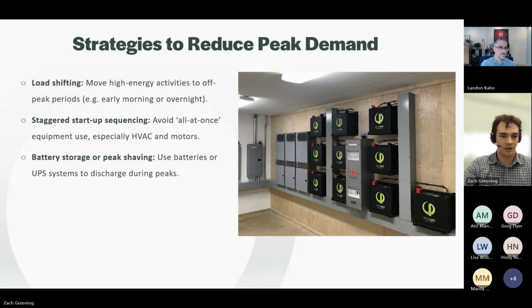The third strategy is battery storage and peak shaving. Battery systems, like the one pictured, can discharge stored energy during identified peak times, reducing your draw from the grid and helping you avoid peak demand fees. It's especially potent paired with something like rooftop solar to maximize self-consumption of energy. If you've done an energy audit or your BMS tells you when the usual energy peaks are, that's when you want to deploy that stored energy from your battery.